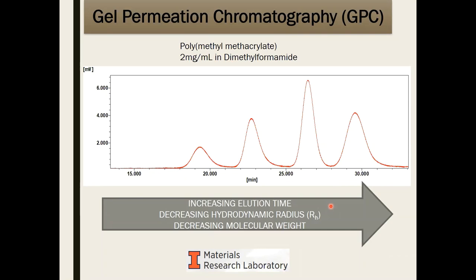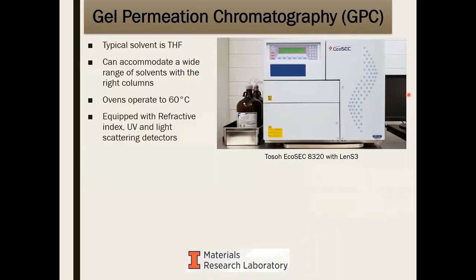The instrument we have at MRL is a Tosoh Ecosec 8320. The typical solvent for GPC is THF (tetrahydrofuran) — it's very common, dissolves many polymers, and is why it's generally used. However, you can run other solvents as long as you have the correct columns. Since columns are generally made of cross-linked polymers, if the solvent severely affects that polymer, you won't get efficient separation and could potentially destroy the column. Always pair the solvent with the right column.